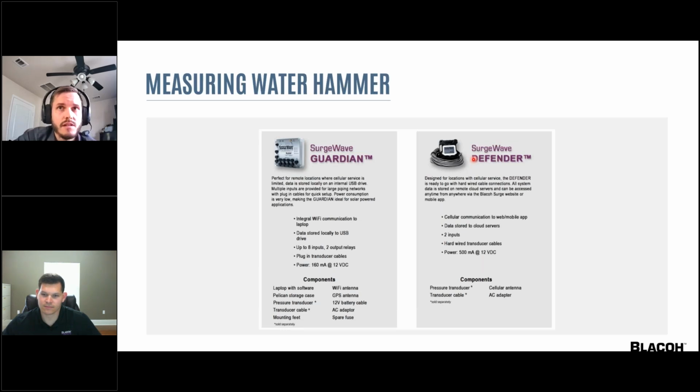As we saw on the previous slides where we were zooming into the data, it can be categorized as steady state data or transient data. Both of these devices watch the data at 500 to 1000 hertz to see which category the data fits into. They record pressures in steady state mode at a typical rate such as 1 hertz per second.